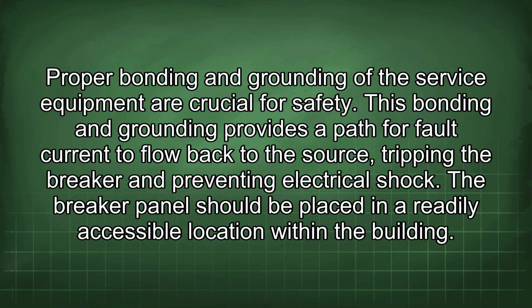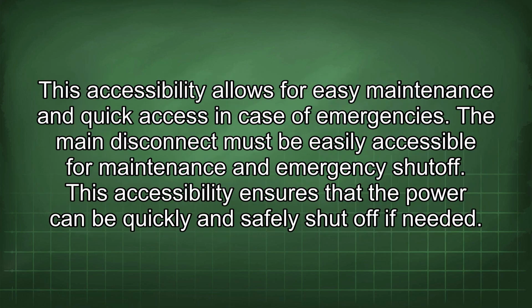Proper bonding and grounding of the service equipment are crucial for safety. This bonding and grounding provides a path for fault current to flow back to the source, tripping the breaker and preventing electrical shock. The breaker panel should be placed in a readily accessible location within the building. This accessibility allows for easy maintenance and quick access in case of emergencies.